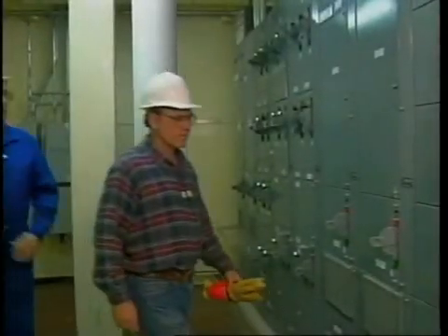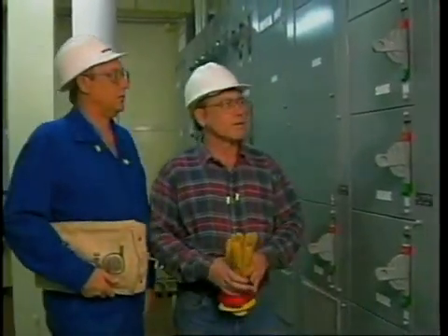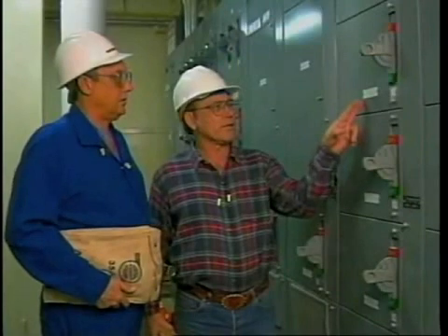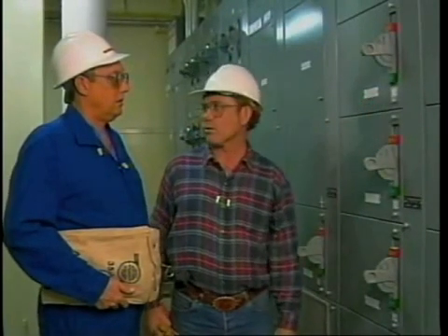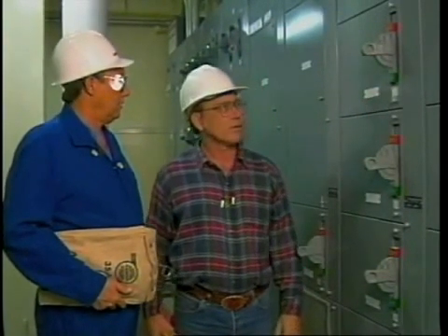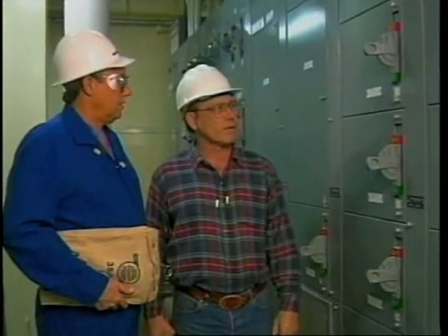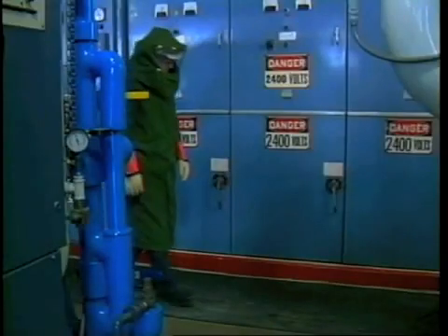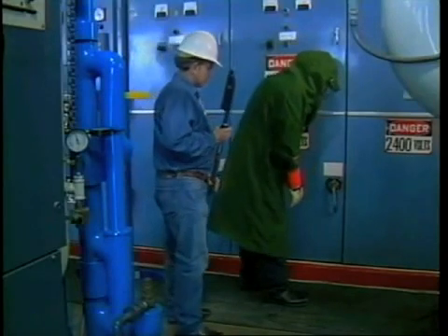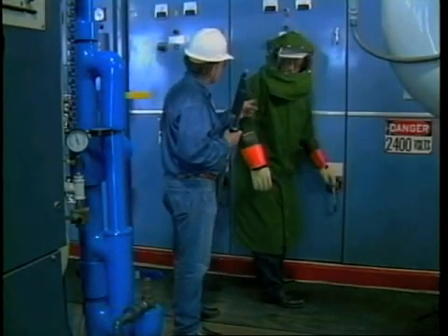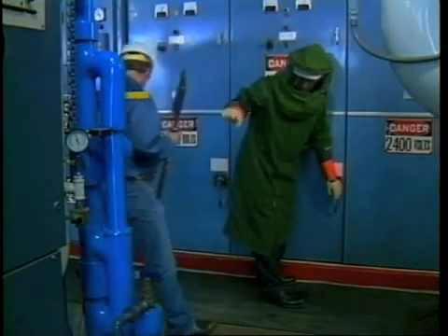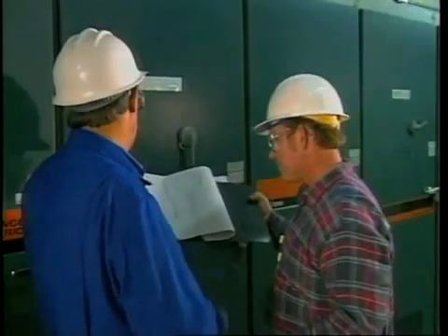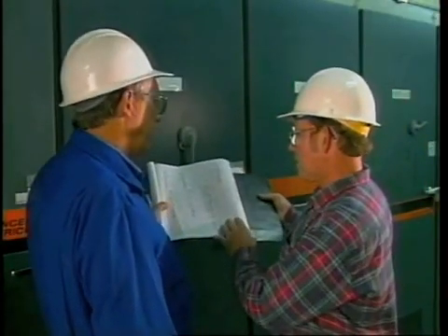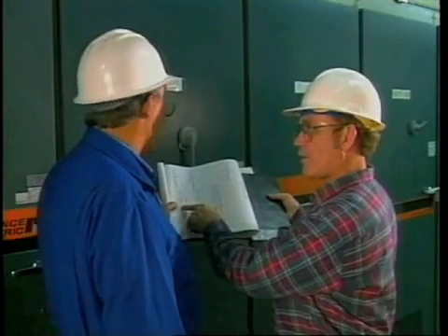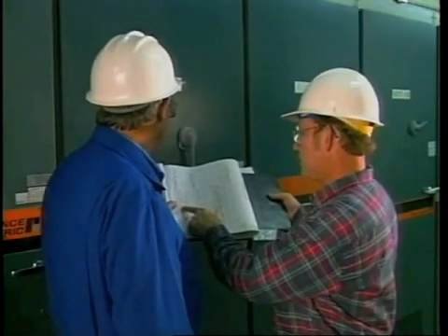Motor control centers are designed to house electrical equipment that start and stop motors, provide overload protection, interrupt short-circuit conditions on motor leads, and allow local or remote operation of contactors. In this program, we'll cover generally accepted safe work practices for working with this type of equipment. Check your location standards and the manufacturer's recommended procedures before doing any work on motor control centers.